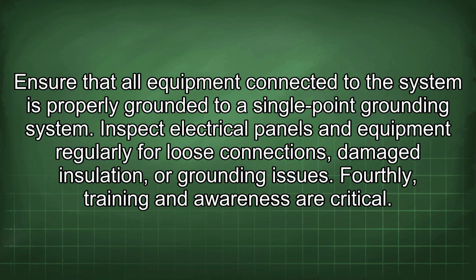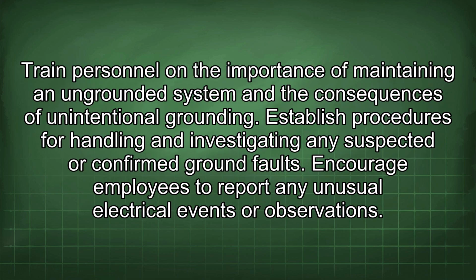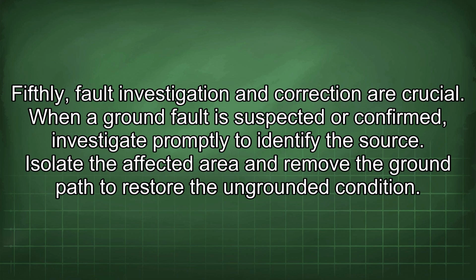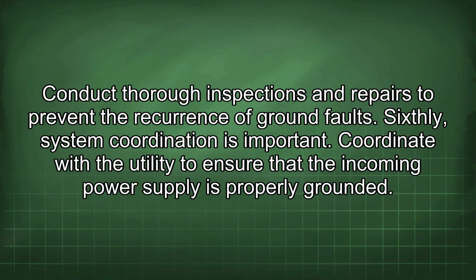Fourthly, training and awareness are critical. Train personnel on the importance of maintaining an ungrounded system and the consequences of unintentional grounding. Establish procedures for handling and investigating any suspected or confirmed ground faults. Encourage employees to report any unusual electrical events or observations. Fifthly, fault investigation and correction are crucial. When a ground fault is suspected or confirmed, investigate promptly to identify the source. Isolate the affected area and remove the ground path to restore the ungrounded condition. Conduct thorough inspections and repairs to prevent the recurrence of ground faults.